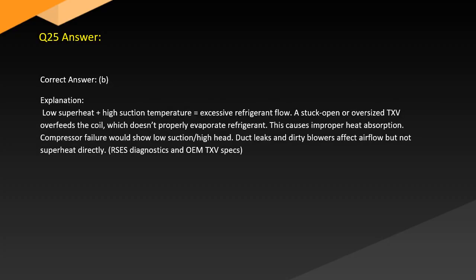Answer. Correct answer, B. Explanation. Low superheat plus high suction temperature equals excessive refrigerant flow. A stuck open or oversized TXV overfeeds the coil, which doesn't properly evaporate refrigerant. This causes improper heat absorption. Compressor failure would show low suction, high head. Duct leaks and dirty blowers affect airflow but not superheat directly. RSES diagnostics and OEM TXV specs.